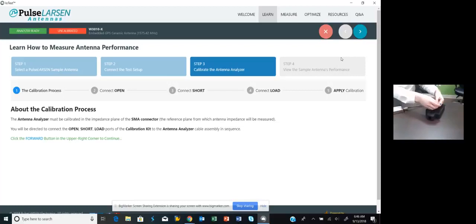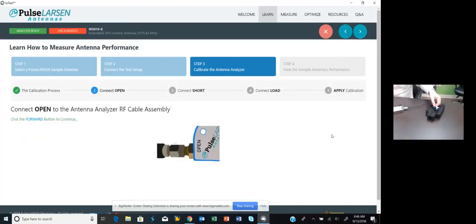I'm going to take my calibrator. It explains a little bit about the calibration process. I should hit the next button. It tells you first you connect the open. I've just done that. I've connected the open. All 3 ports are labeled. There are 3 ports to the calibrator. I've clicked my open port right here. I'm going to select next.